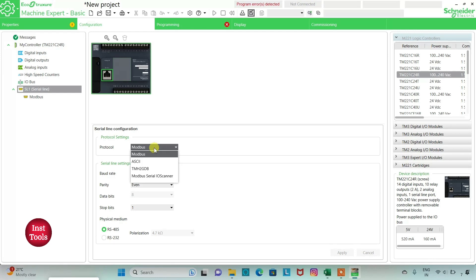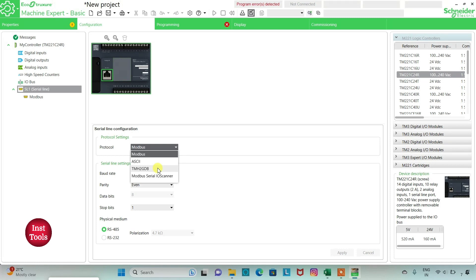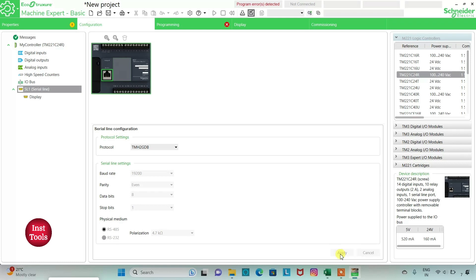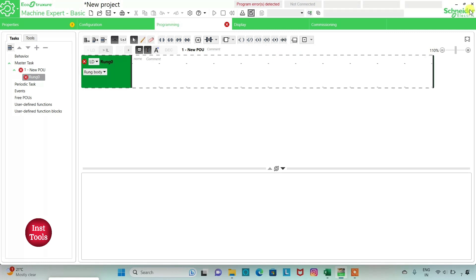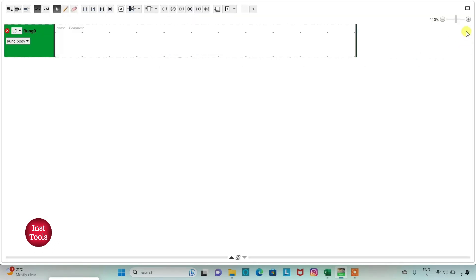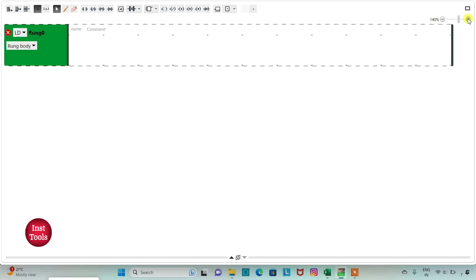I will also go to serial line and select the protocol. Options include Modbus ASCII, TMH2GDB, or Modbus serial IO scanner. I will select TMH2GDB and click apply. Then I will go to the programming tab where we will draw a ladder logic and use memory bits. I can click the full screen option and zoom in or out as needed.